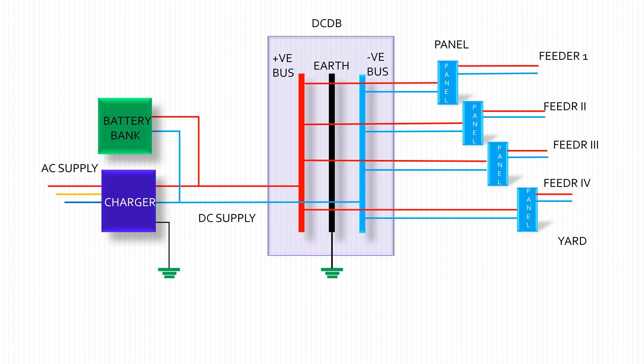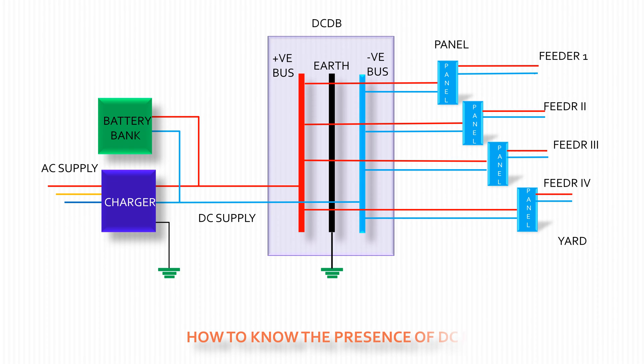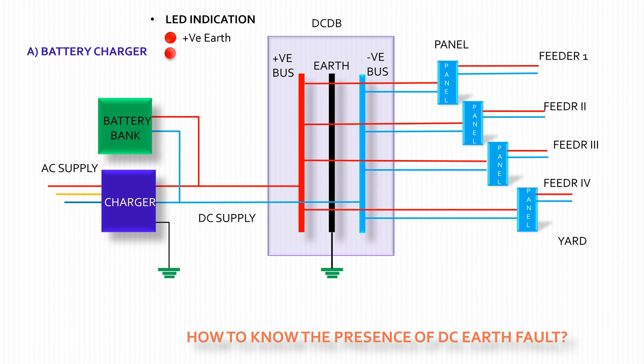DC earth fault may occur at any part of the circuits. If an earth fault occurs at any part of the circuit, the total system becomes faulty. To know the presence of a DC earth fault: from the battery charger — LED indication and earth fault relay operation, if any.